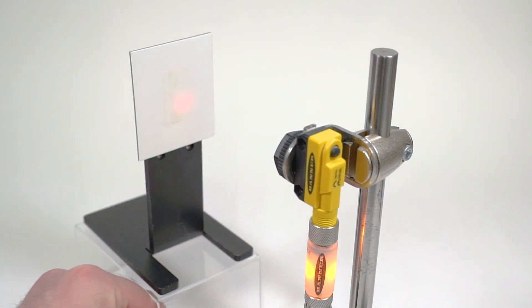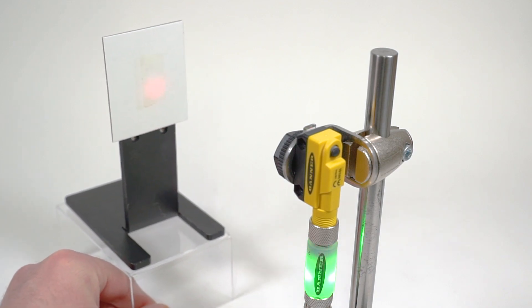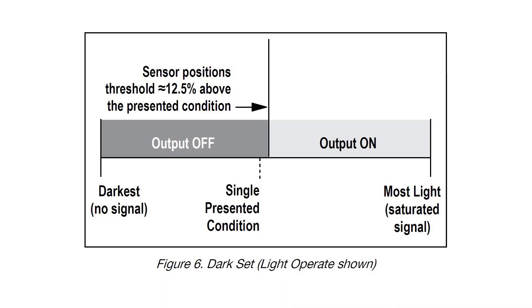The dark set mode works in the opposite way. It measures the light returning to the receiver and sets the switching threshold 12.5% above the taught condition.